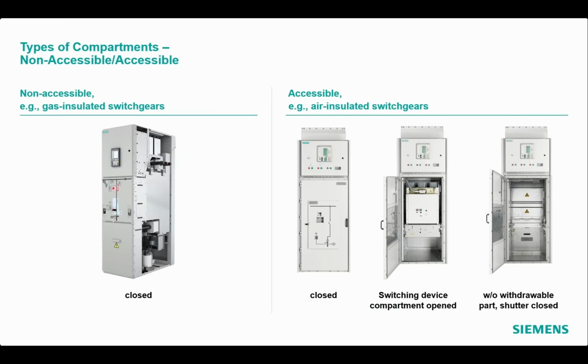On the right side, you can see a panel of an air-insulated switchgear. The first picture from left shows the panel where the switching device compartment is closed. In the second picture, when the compartment is opened, there is a possibility to access the switching device, in this case, the withdrawable circuit breaker. In the third picture, when the circuit breaker is completely withdrawn outside, the shutter is closed and the compartment is fully accessible.